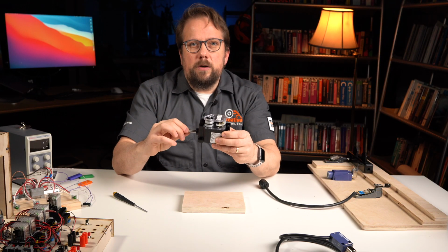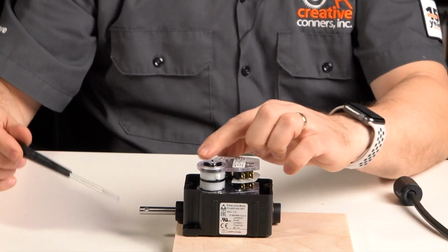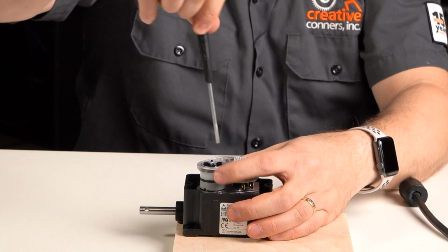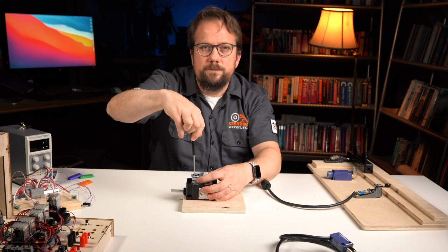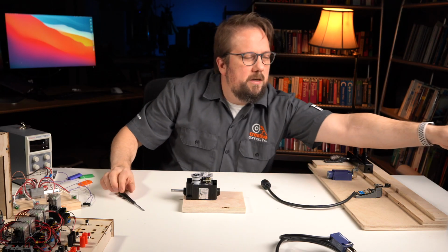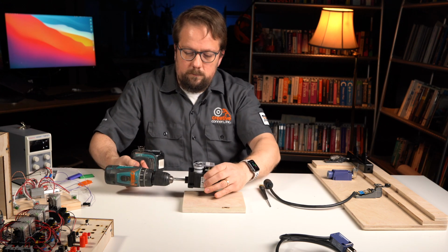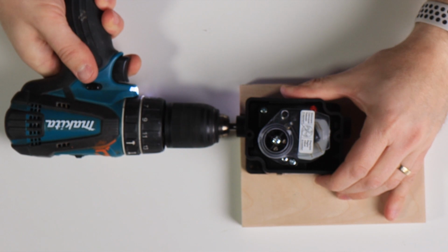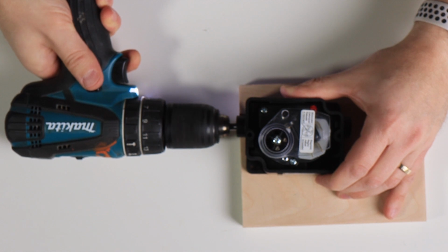The selected gear ratio gets you in the ballpark of the correct range of motion, and then you can adjust the exact angle of the cams with a screwdriver to really dial in the position of these limit switches. Let me run this with a drill so you can see it work. Now, instead of a drill motor, imagine that this was connected to a hoist or a winch drum.